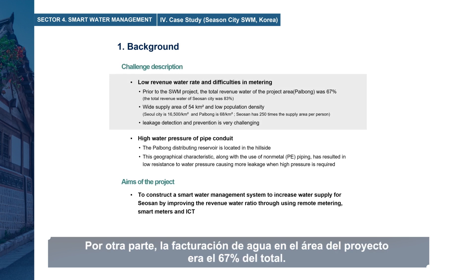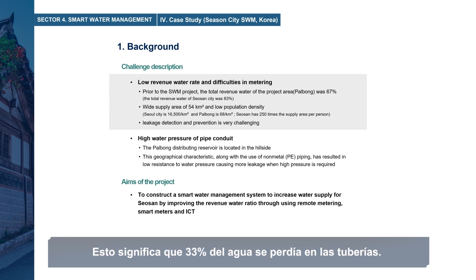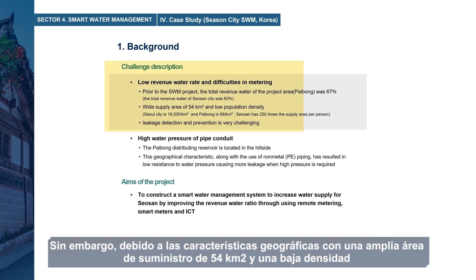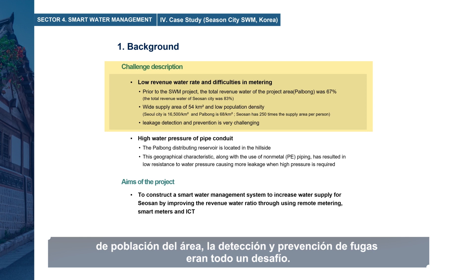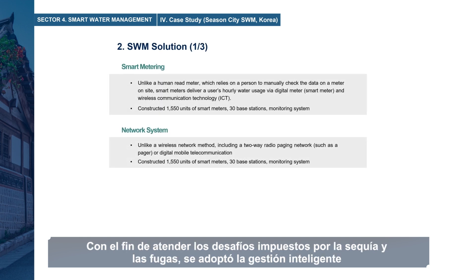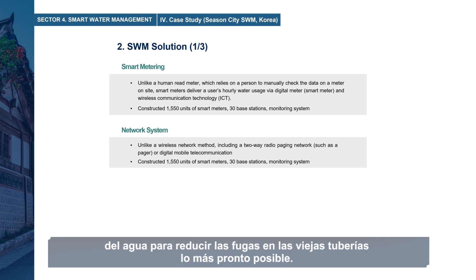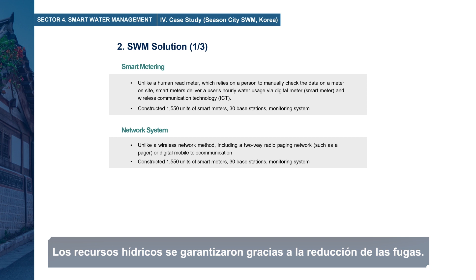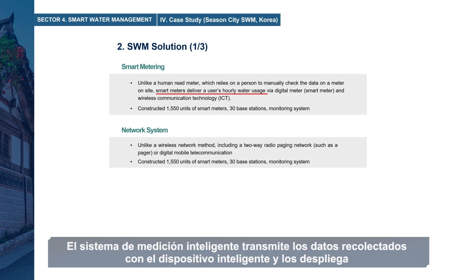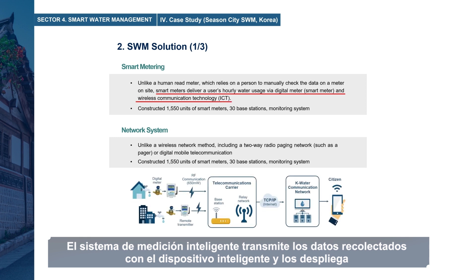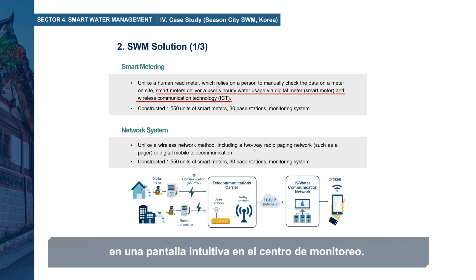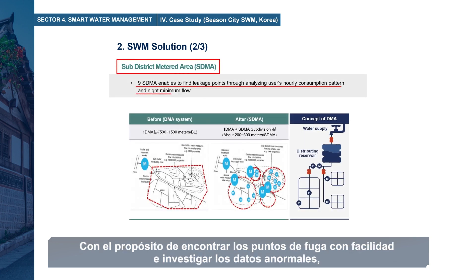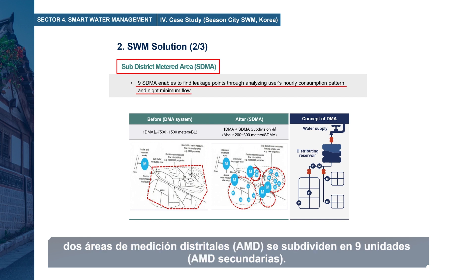Moreover, the total revenue water of the project area was 67%, meaning 33% was lost in the pipes. However, due to geographical characteristics — a wide supply area of 54 square kilometers and low population density — leakage detection and prevention were very challenging. In order to address these challenges, smart water management was adopted to reduce leakage in aged pipes as soon as possible. The smart metering system transmits collected data from smart devices and displays the data on a user-friendly display in the monitoring center. The two existing District Metering Areas, DMAs, were subdivided into 9 sub-DMAs.